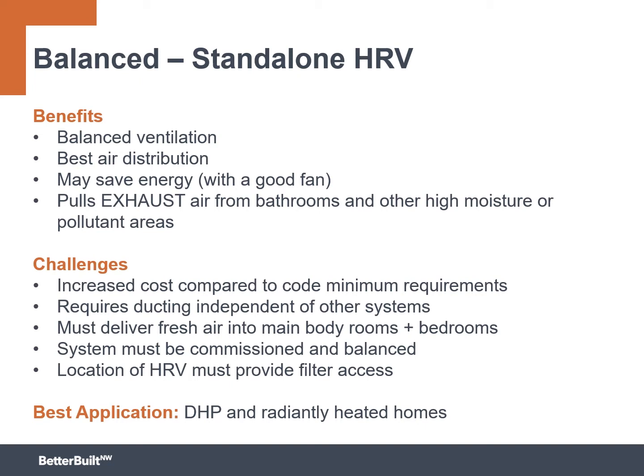Well, all of them technically do according to the code, but these can be a little challenging depending on the brand and the location of the equipment. And the location of the HRV itself needs to be in a place where basic maintenance can be done, particularly access to filters. Now, this is generally a really good strategy for homes that use something like ductless heat pumps or radiantly heated homes or any type of heating and cooling system that is not inherently central and already distributed. If you have enough space, you can also put this in with a home with a central air handler, like a furnace or central heat pump. You're just running twice as much ductwork.